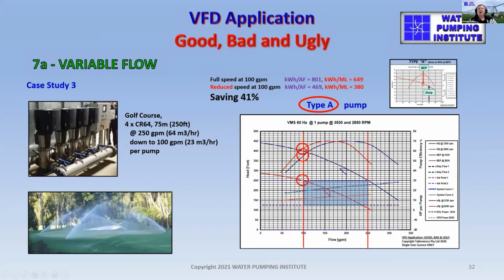Let's start with a type A pump, the more common pump that's out there, where the duty is to the right-hand side of the best efficiency point. So we start off here. There's the full speed pump here. There's its best efficiency point, and this is the duty. So we're now looking to run this pump in this area of flow at that same pressure.